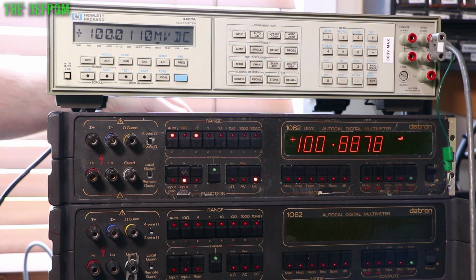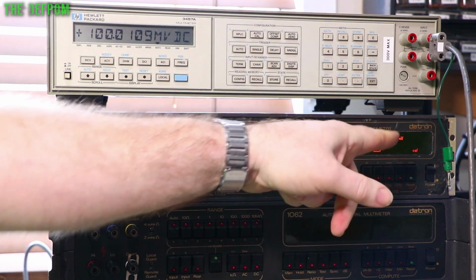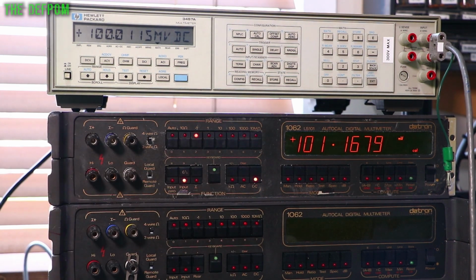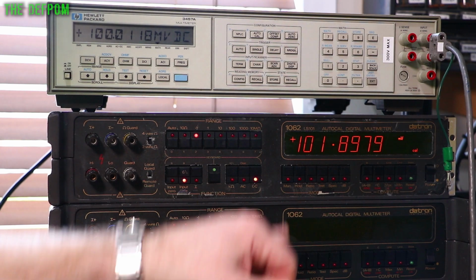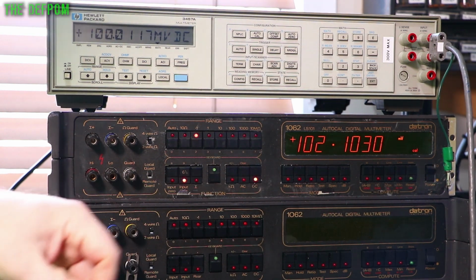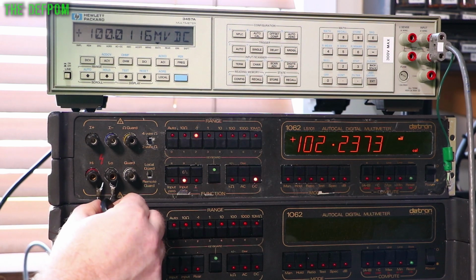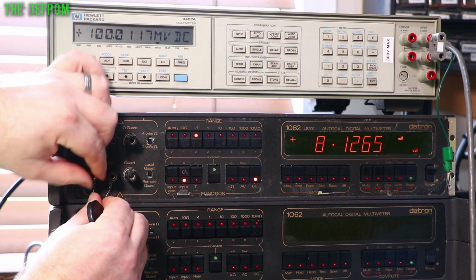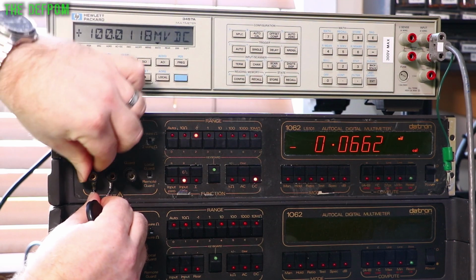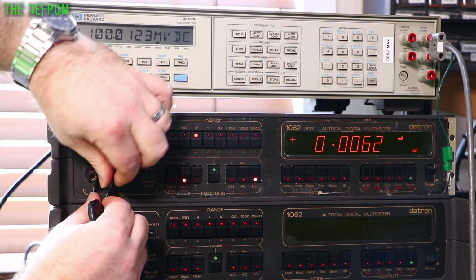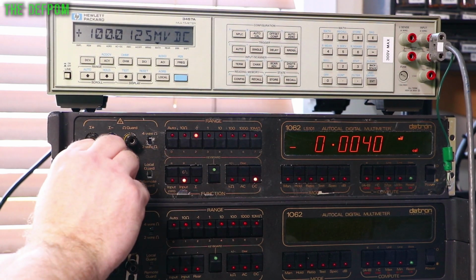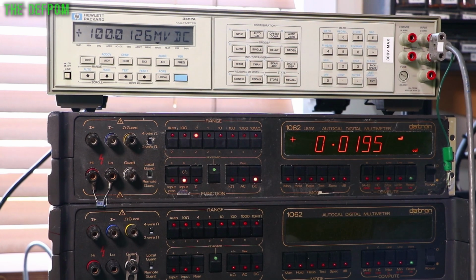All right, so let's get this thing going. I've got to flick the calibration switch on the back. There we go, now in calibrate mode. I need to go to the 0.1 volt scale, which is what I'm already on. DC, I'm already on that. Filter is in, that's already on. So now I need to do the linear button. Linear is this one over here, linearity. What I've got to do is put the little 1 megohm across here. This is what's required first. Put it down nice and solid. Nice, there's 1 megohm across there. And now I've got to do the linear button.